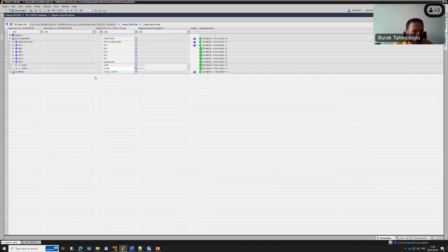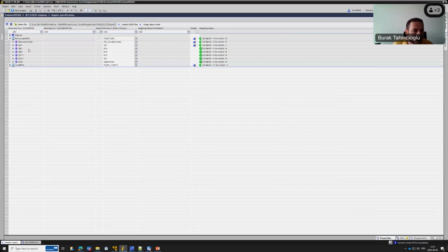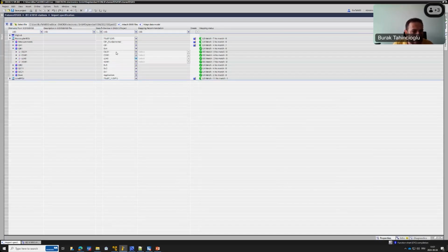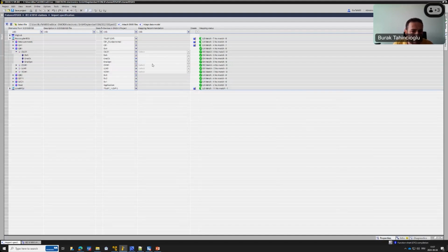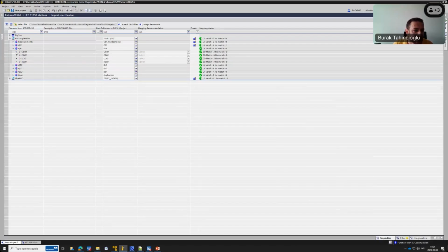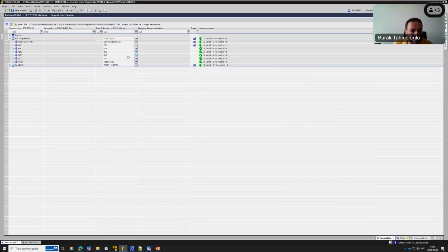Why isn't it found? Most probably we have the name LPHD1, but Siemens offers the name LPHD0. But now we have a perfect match for the root logical node. All logical nodes, even under the data objects, are completely matched down to the data attribute level. So whatever we specified is matching, with only one exception: QA1 and the measurements.